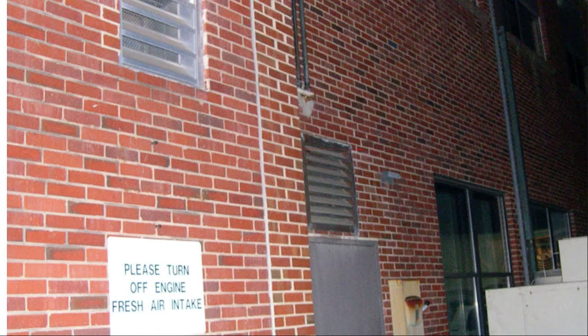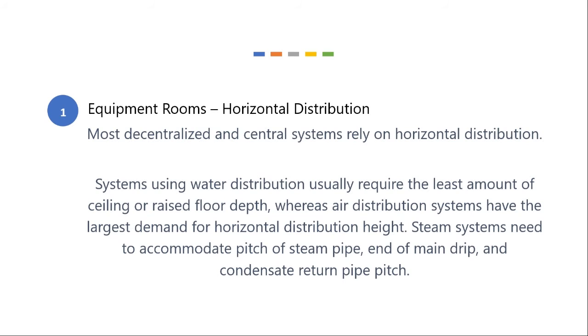So if we look at this photo, for example, we have an air intake here. If fresh air enters the building through this vent, through this intake, obviously they put in a sign here. It says to turn off your engine because dirty air can come in through this intake. Or somebody could play a prank on you and introduce something toxic into the air. Or if this intake was closer to the ground and it snowed, the snow could cover up the intake and the building wouldn't get any fresh air.